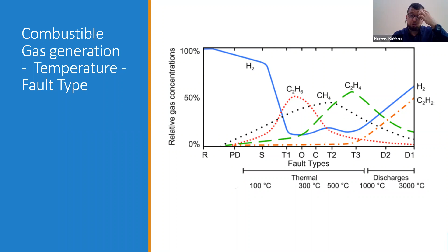Now, from the results you compared them with the IEC limitations given in the back slide, this slide I'm referring to, the recommended gas limits, and you came to a finding that results are not right. Results are on the higher side, and rate of rise is high, or absolute gas limits are high, and they are higher than the last DGA results. So, is there a fault or not? If there is a fault, then what type of fault is it? Now you have come to the fault identification step.